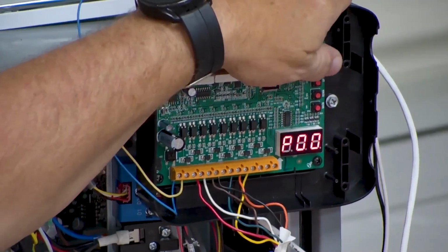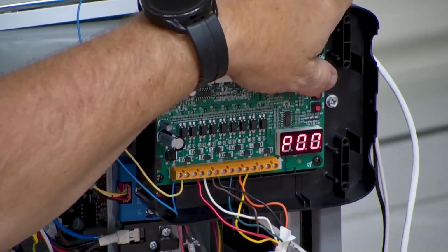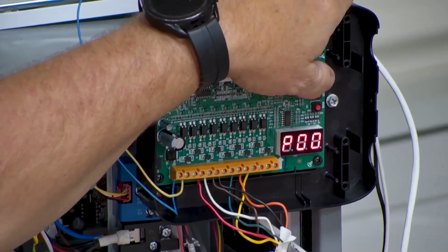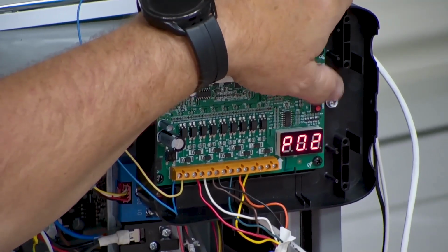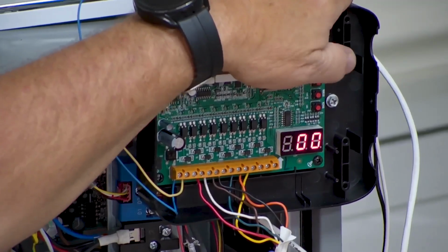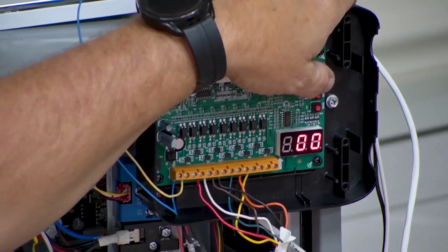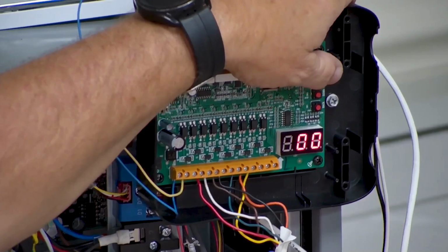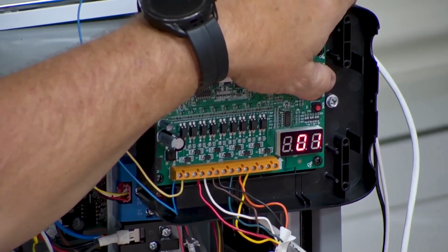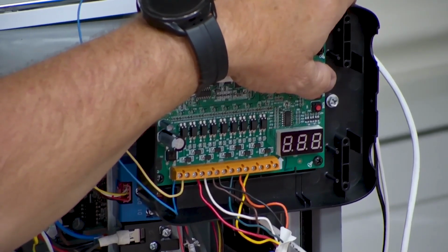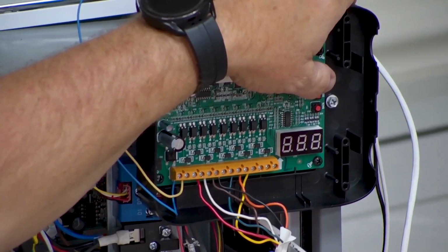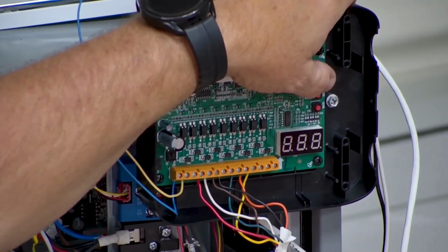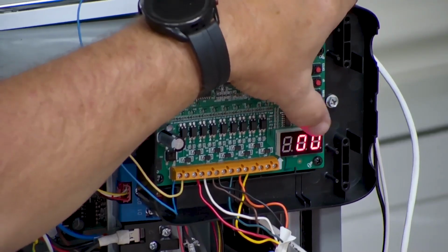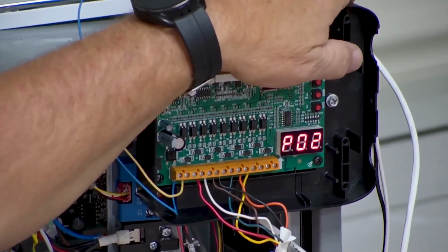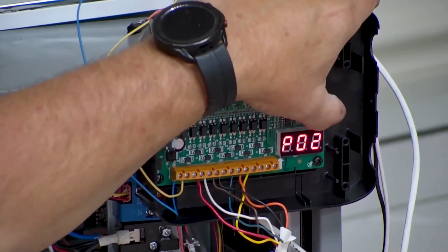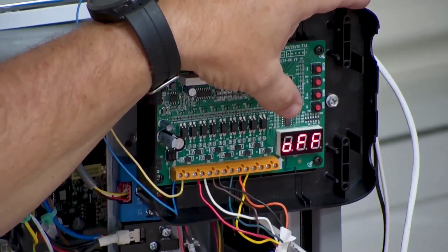So if you hit enter, and then it'll come up P00. I went up one time to P02. I hit enter again. Now 00, Daniel, help me out, is what again? 00 is auto. Okay, and then 01 is? Low speed. 02 is medium speed. And 03 is high speed. Okay, and we'll put it back the way it was. So now they got it blinking. That's what it's set to. I hit enter again. Now it saved it. Then I can hit the back key. It takes me back to the main screen.